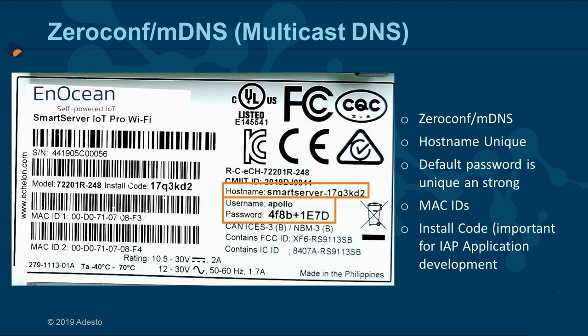You must know that in the first customer shipment there is no facility to recover a lost password. In the 2.50 release and beyond, a 20-second press of the service pin will create a period of 120 seconds for anonymous access so that the password can be changed. Also on the back you'll find the MAC IDs should you need them.